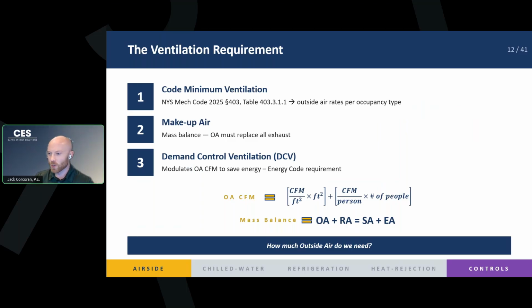In that first equation for the CFM, you have an outdoor rate based on the number of people, and you have it based on your square footage. So if you don't have as many people in the space, theoretically, you can reduce the amount of outside air CFM you're bringing in, and that's exactly what demand control ventilation does. It's just a modulating CFM of outside air instead of a fixed value, and that, as we'll see, has energy saving implications, just because you're not cooling all that hot and humid or very cold and dry air.